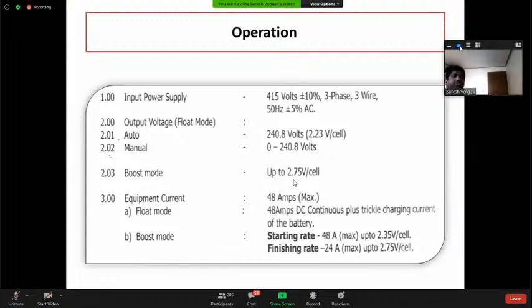In boost mode, each cell is at 2.75 volts. In float mode, it is at 48 amperes. DC continuous means 48 amps load is required plus trickle charging. So your charger should have the facility for at least this much load. So while sizing the charger, the criteria is you need to charge your battery plus supply your load. That is the criteria for sizing the charger.